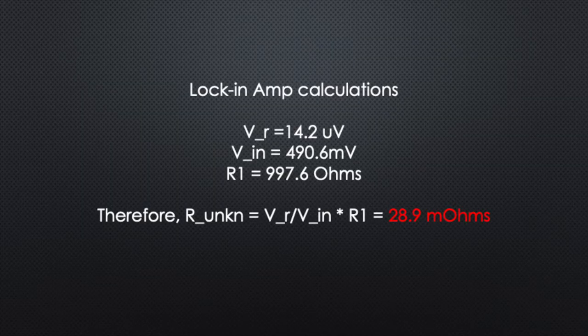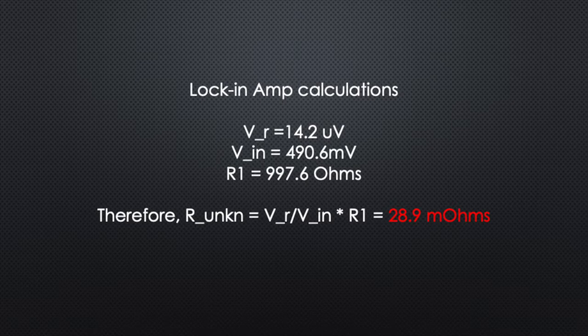Here are the calculations for the lock-in amp resistance. VR was 14.2 microvolts approximately, VIN was 490.6 millivolts, R1 was 997.6 ohms. Therefore, R unknown from our calculation formula earlier came out to be 28.9 milliohms. We'll compare this with a couple of other measurements we do later on.